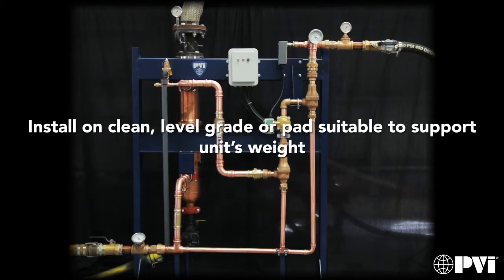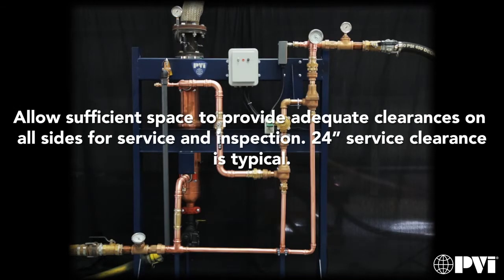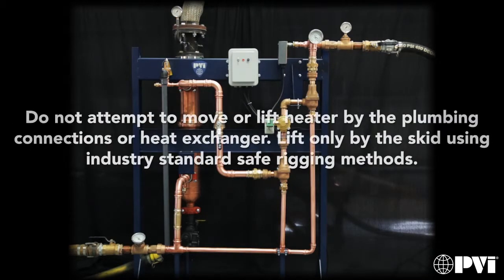Install on clean level grade or pad suitable to support unit's weight. Provide adequate clearance on all sides for service and inspection. 24-inch service clearance is typical. Do not attempt to move or lift heater by the plumbing connections or heat exchanger. Lift only by the skid using industry-standard safe rigging methods.